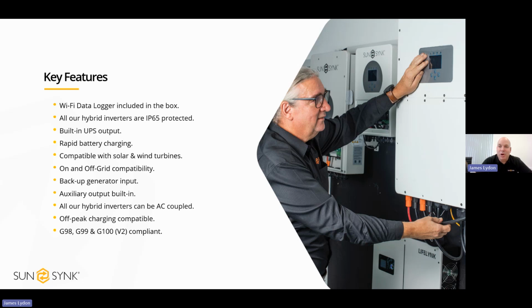Quick recommendation on backup generators. We don't have a preferred brand that we work with. Just make sure it's a decent make. When sizing the backup generator, we always recommend oversizing it a minimum of 150% on top of the size of the inverter. So if you've got a 5 kilowatt hybrid inverter, what you don't want to do is add a 5 kVA Jenny to it.